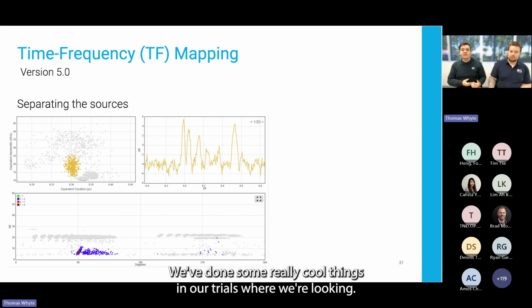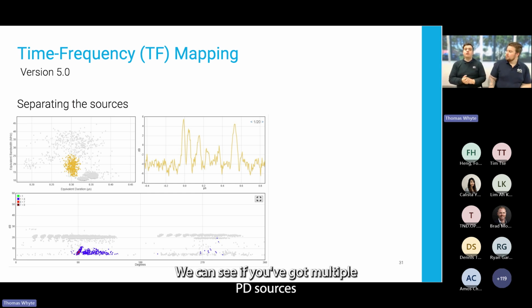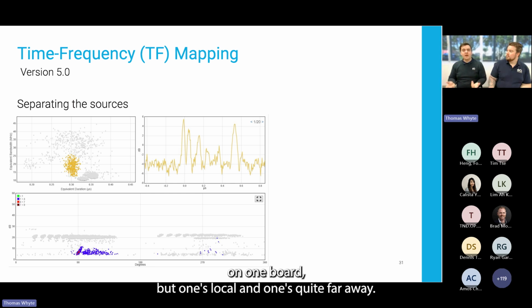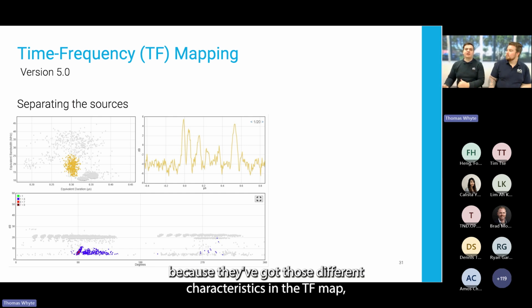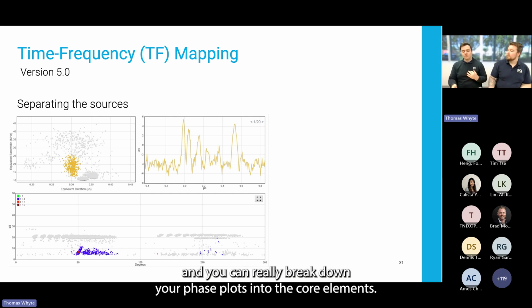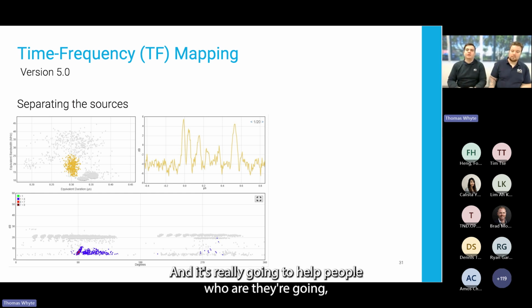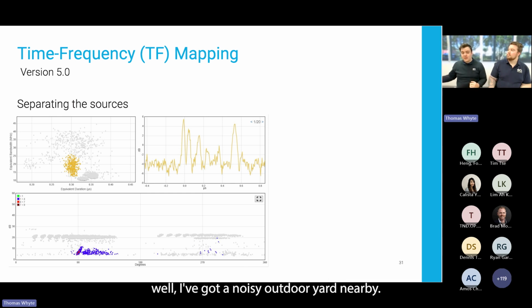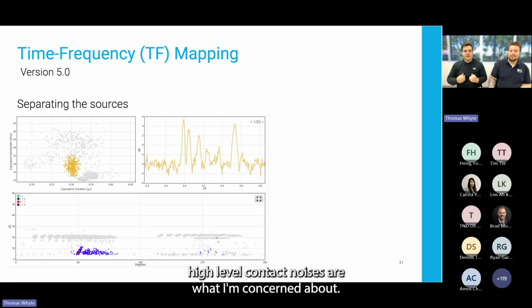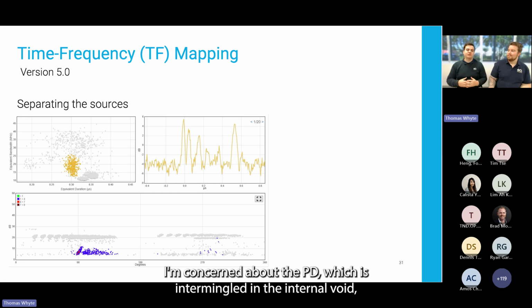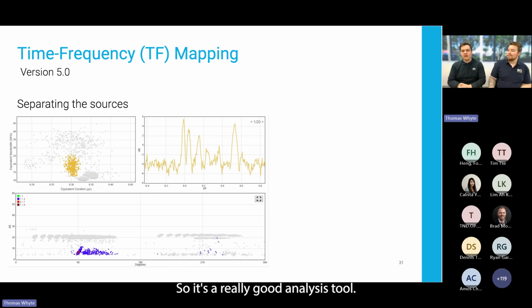We've done some really cool things in our trials where we can see if you've got multiple PD sources on one board, but one's local and one's quite far away, you can even separate them because they've got those different characteristics in the TF map. And you can really break down your phase plots into the core elements. It's really going to help people who are going, well, I've got a noisy outdoor yard nearby, it's impinging. Those high-level contact noises aren't what I'm concerned about. I'm concerned about the PD, which is intermingled in the internal void with those. So it's a really good analysis tool, but it's available back in the office, not on the device itself.